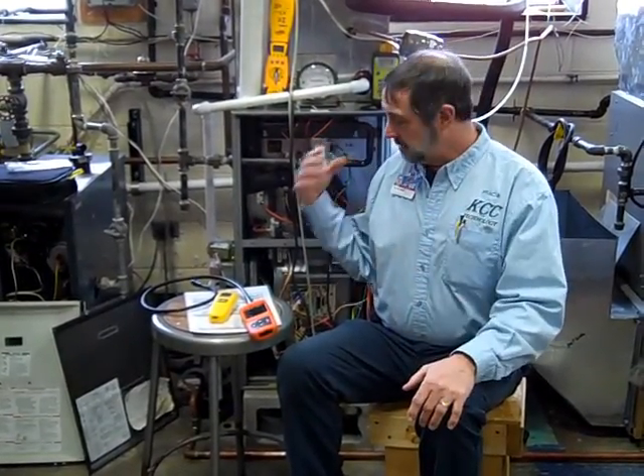He disassembled the furnace, he was inspecting the heat exchanger, testing the pressure switches. All of those tools that we've been using, you basically see he's been using too. Now remember, use all the tools that you have. You're going to be looking at dual port manometers and magnehelic gauges and something to take temperature rise. Remember what I said about temperature rise.